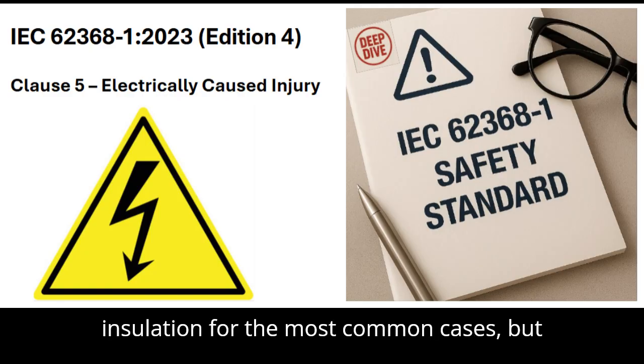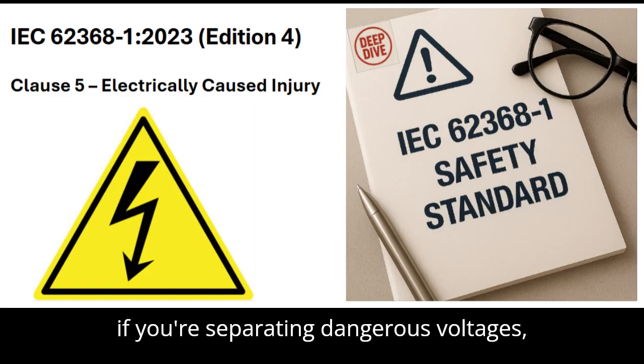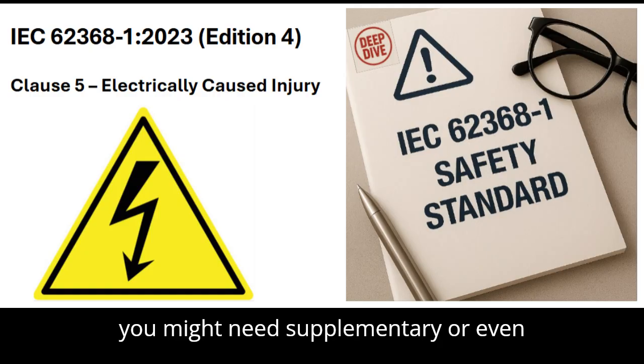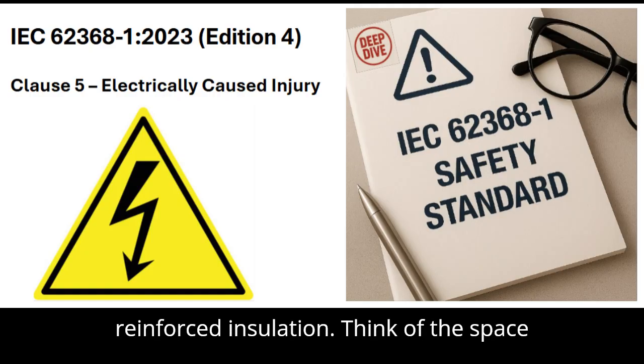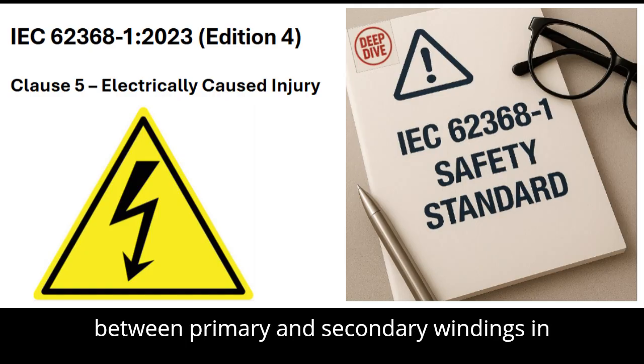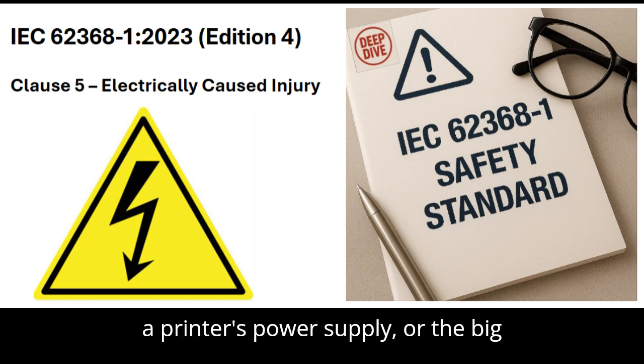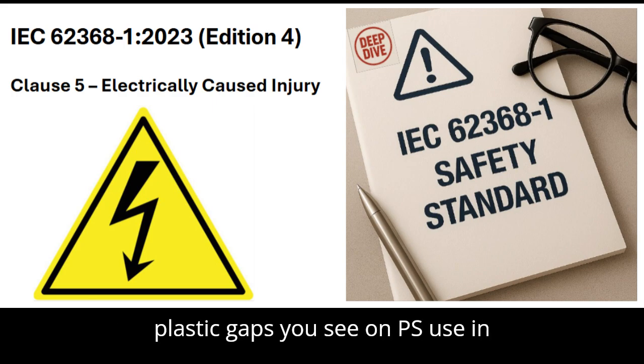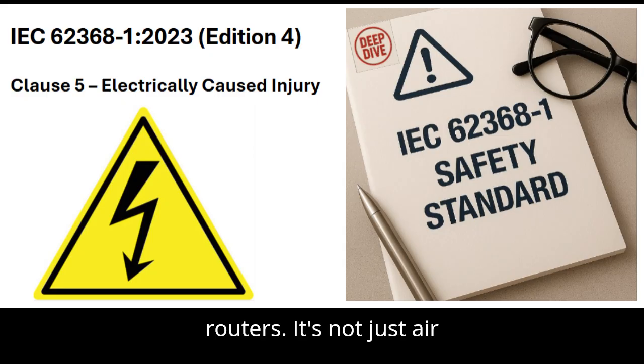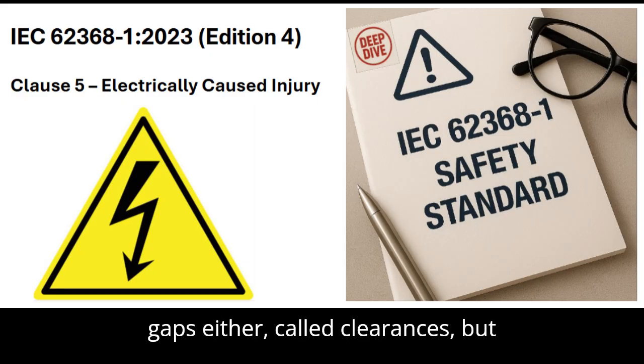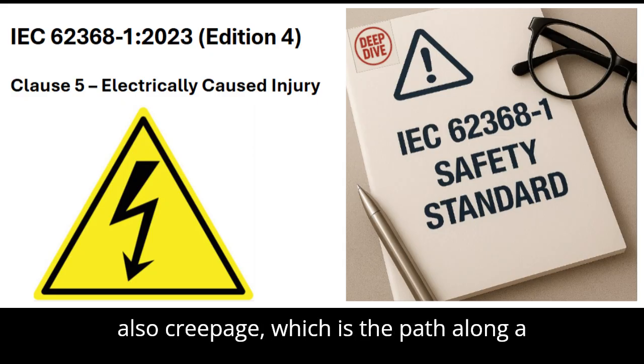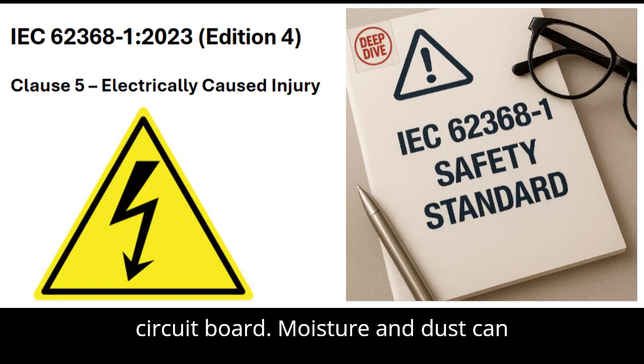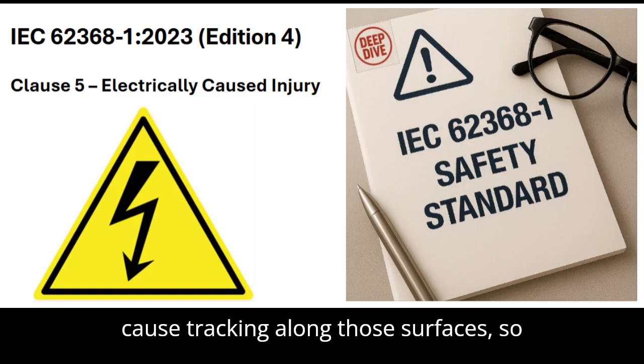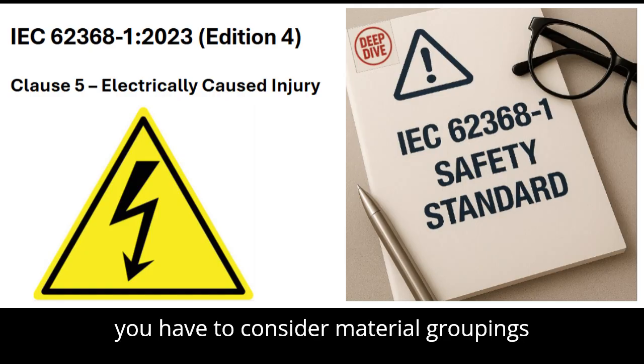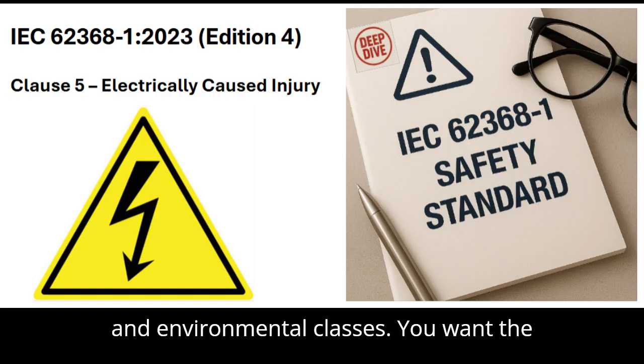You need basic insulation for the most common cases, but if you're separating dangerous voltages, you might need supplementary or even reinforced insulation. Think of the space between primary and secondary windings in a printer's power supply, or the big plastic gaps you see on PSUs and routers. It's not just air gaps either, called clearances, but also creepage, which is the path along a circuit board. Moisture and dust can cause tracking along those surfaces, so you have to consider material groupings and environmental classes.